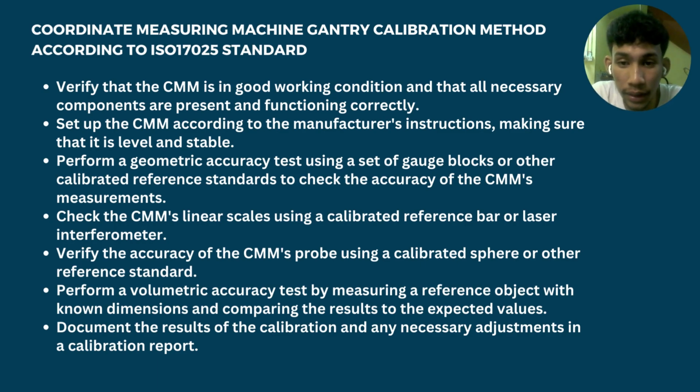Secondly, set up the CMM according to the manufacturer's instruction manual, ensure that it is level and stable, and perform a geometric accuracy test using a set of gauge blocks, or other calibrated reference standards to check the accuracy of the CMM measurement.